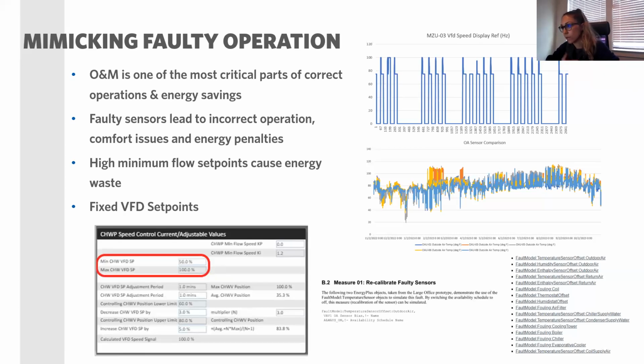Now you increase the redundancy, so if one of them goes bad, at least the other one is working fine. But at some point, you also need to make sure that they're not more than 2 degrees apart from each other. Because I know when I was in the building, they were all placed at the same level in similar areas. So there's no way they can have this much of a difference in the outside air reading. And this is not even comparing to the AMY data. This is just a comparison between each other.